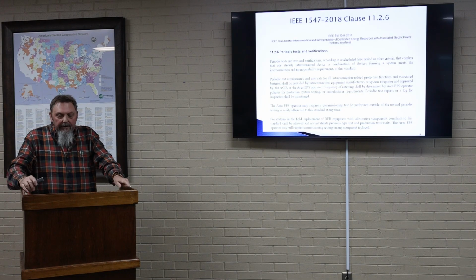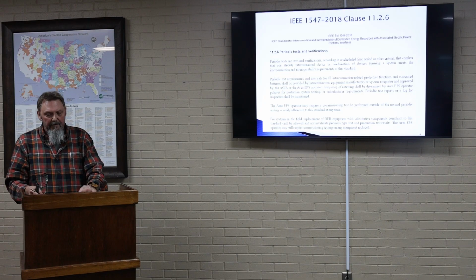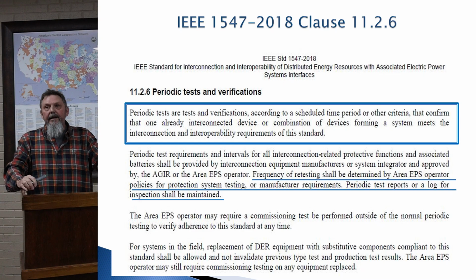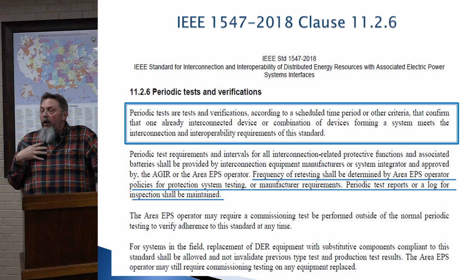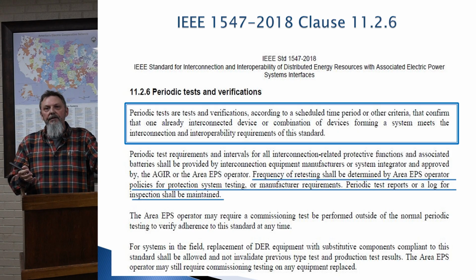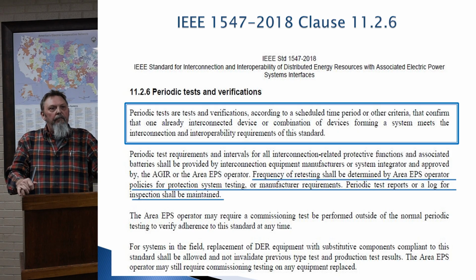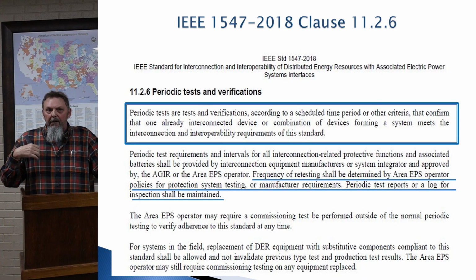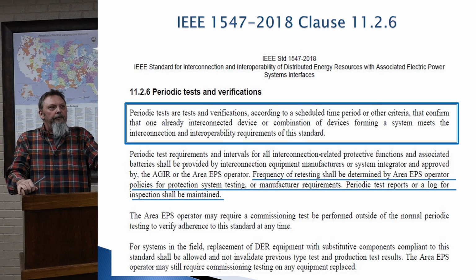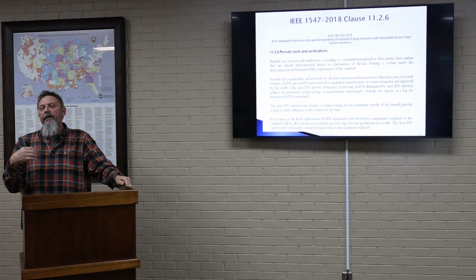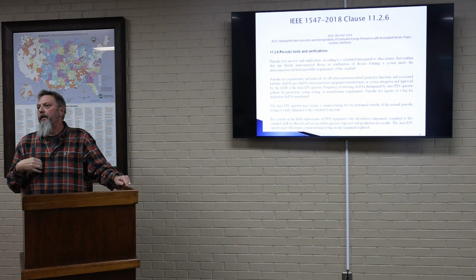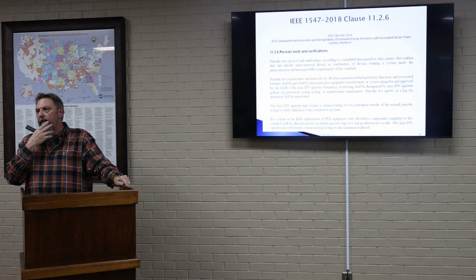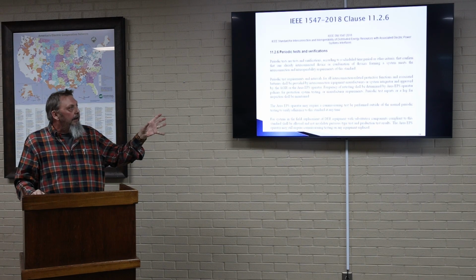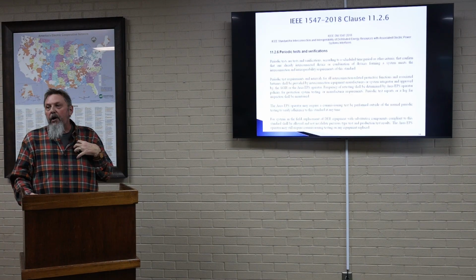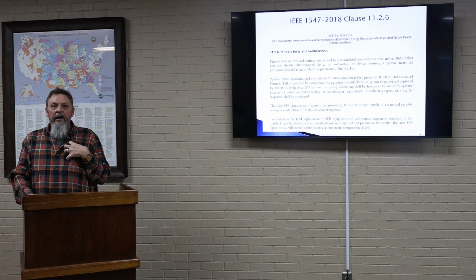The other point we talk about is testing. That comes from the IEEE standard that requires an annual test to make sure your inverter shuts off within 2 seconds when you lose power from the grid. We send out a letter asking you to send us those test results. You're supposed to do it each and every year, and we ask for that log to see if you've tested it or not. If you haven't, then you need to go ahead and test it. That is developed from the standard that says we as a co-op can dictate what that frequency is.